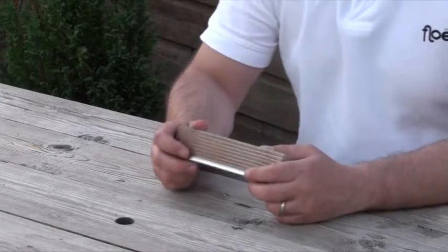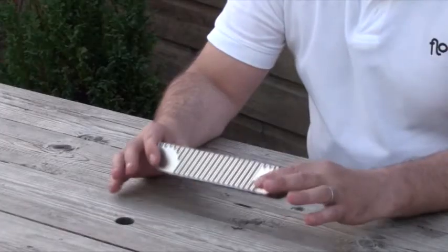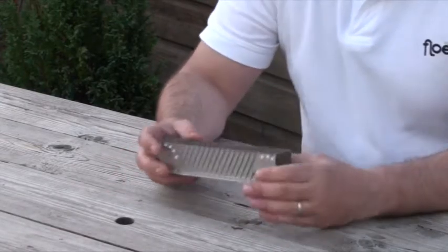Now, what I mean by that is, on a typical boiler, you will have these. These are called heat exchangers. Generally, in a combi boiler, you will have two of them. One of them, say it's up top, will heat up the water that goes around your radiator loop. Generally that loop of water is a sealed loop and it will have antifreeze in it, obviously to prevent frost. There is a lower heat exchanger, and what that will do is heat up the fresh cold water that comes into the boiler and then goes on to all of your hot taps and faucets and showers, etc.